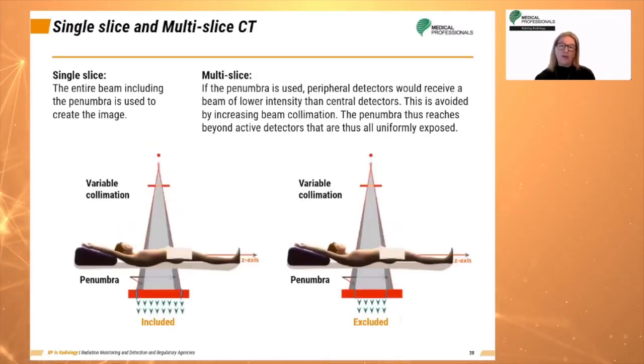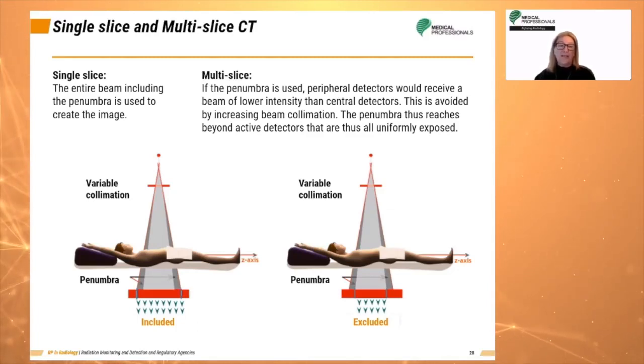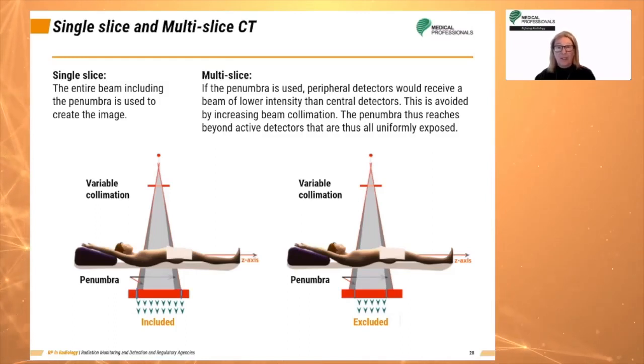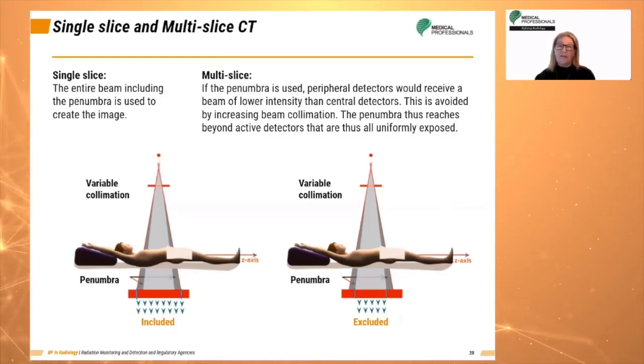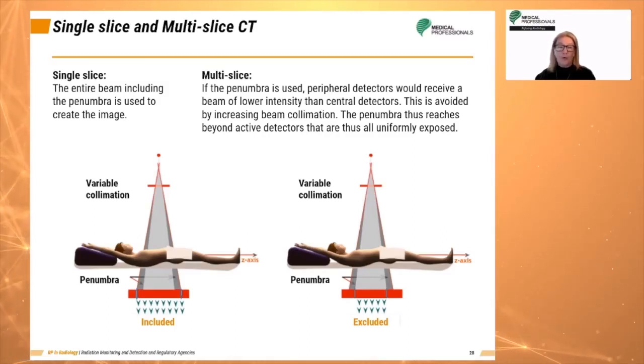Let's talk about single-slice and multi-slice acquisitions and their differences. In a single-slice CT, the entire beam including the penumbra is used to create the image. However, in multiple-slice CT, if the penumbra is used, the peripheral detectors would receive a beam of lower intensity than the central detectors. This is avoided by increasing the beam's collimation, allowing the penumbra to reach beyond the active detectors so that all are uniformly exposed.